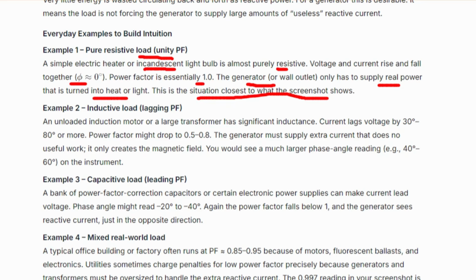Example 2, inductive load with lagging power factor. An unloaded induction motor or a large transformer has significant inductance, so current lags voltage by 30 to 80 degrees or more, and the power factor might drop to 0.5-0.8. The generator must supply extra current that does no useful work; it only creates the magnetic field. You'd see much larger phase angle readings, 40 to 60 degrees, on the instrument.